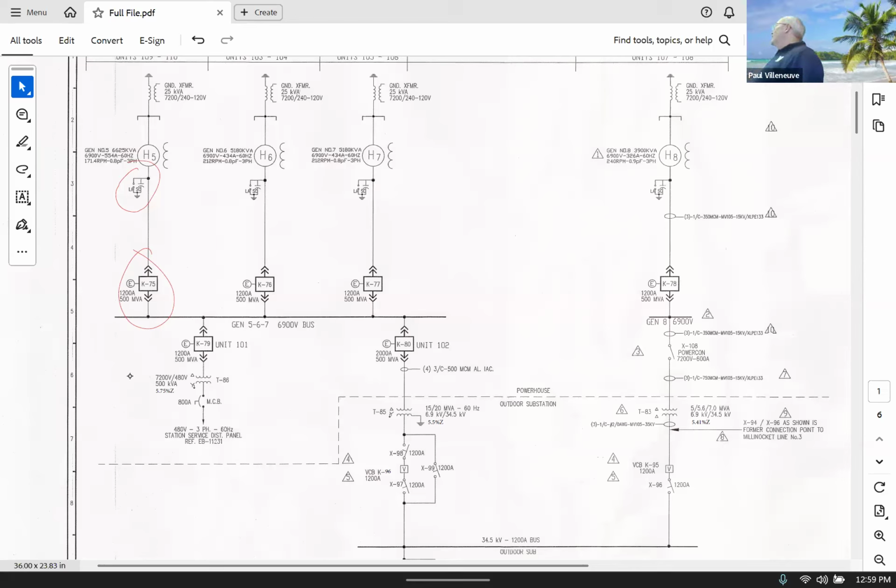When they're conducting to ground, that means that you've had some sort of a high voltage condition on that generator, and you got to shunt that to ground. These are only designed to last for like milliseconds at most. Okay, so that would not be for continuous. We have the generator over here, and that has an internal impedance. This right here is called a field winding. So that's actually how you get magnetic energy.